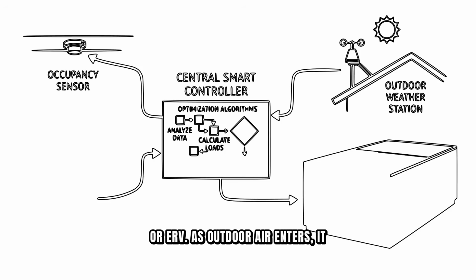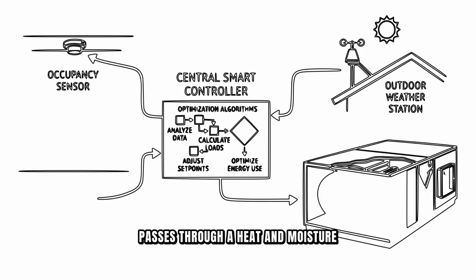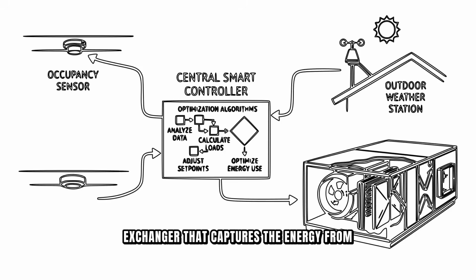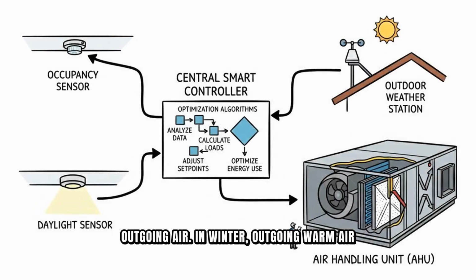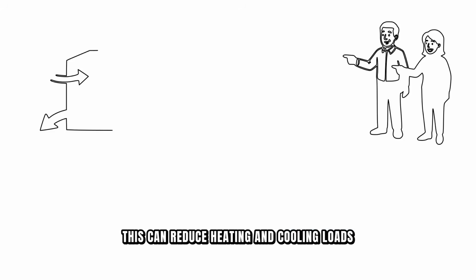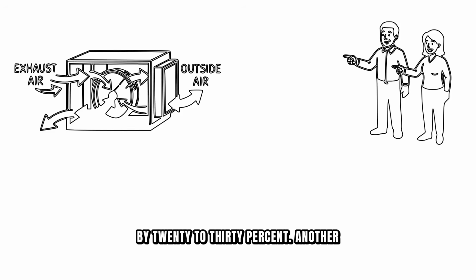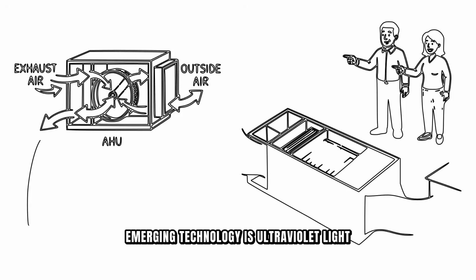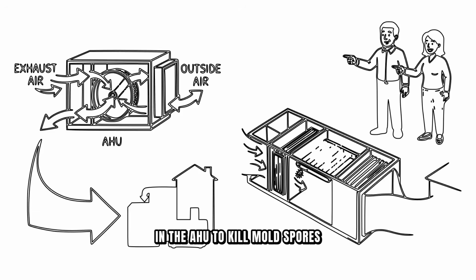Many new units incorporate energy recovery ventilation, or ERV. As outdoor air enters, it passes through a heat and moisture exchanger that captures the energy from outgoing air. In winter, outgoing warm air heats incoming cold air. In summer, outgoing cool air pre-cools incoming hot air. This can reduce heating and cooling loads by 20 to 30%.